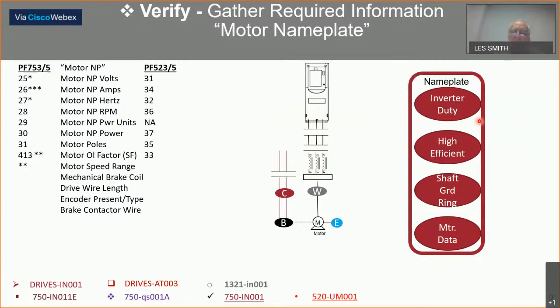Motor speed range, you look at the motor for that. It's 10 to 1 speed range, 2 to 1 if there's no derating, 10 to 1, 20 to 1, 1,000 to 1, 2,000 to 1, depending upon the quality of the motor. But be aware of that so you can watch the process, see how it runs. If you don't stay within those parameters, you're going to get motor overheating and damage.